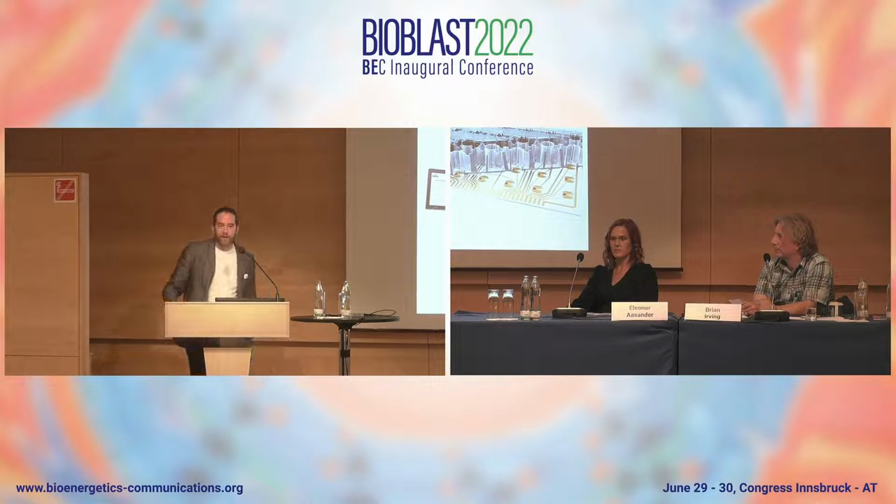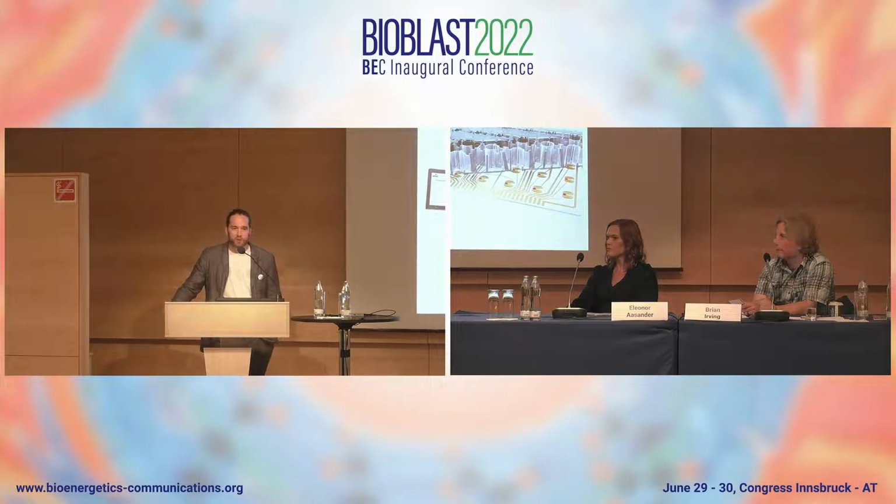Well, we are right at the beginning of going below 5%. At the moment, we just did experiments with around 5% oxygen concentration within the device, just to have a kind of control of what still is possible, because the oxygen consumption needs to be there, and the cells need to have something to live on. Otherwise, we have problems. This 1 to 21% is what the device is capable of, so we cannot go by the device control below 1%. Yeah.